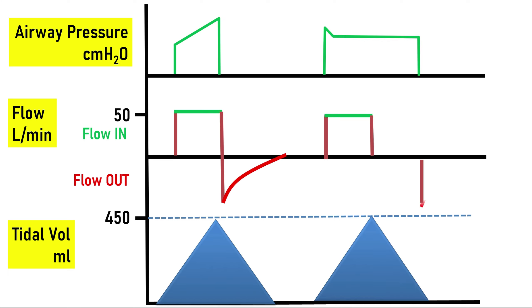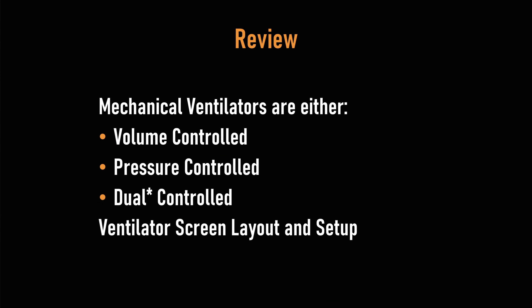The typical waveforms on volume control ventilation: on top is airway pressure — usually positive, measured in centimetres of water. In the middle is flow — positive during inspiration and negative during expiration. On the bottom is tidal volume in mils. Even though the flow and pressure waveforms look different, the tidal volumes are the same, which is characteristic of volume control ventilation. So what I've covered is mechanical ventilators and their control: volume controlled, pressure controlled, or dual controlled (volume guaranteed pressure control), plus the ventilator screen layout and typical waveforms.